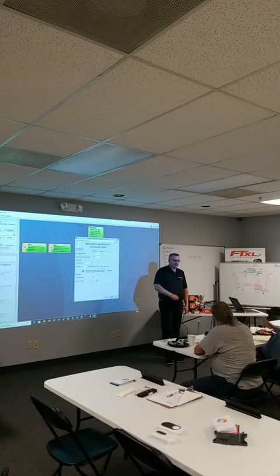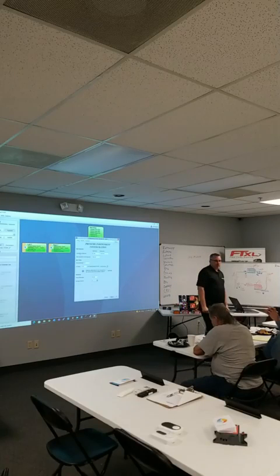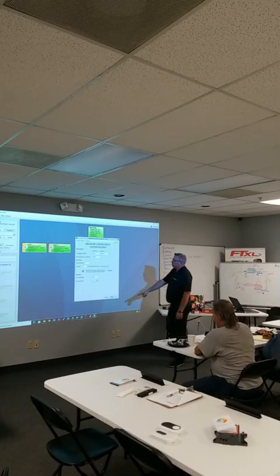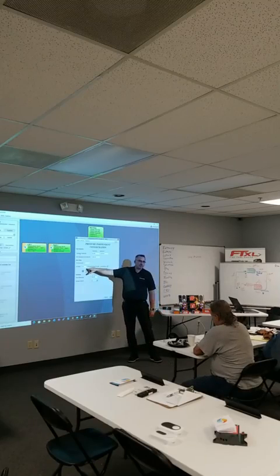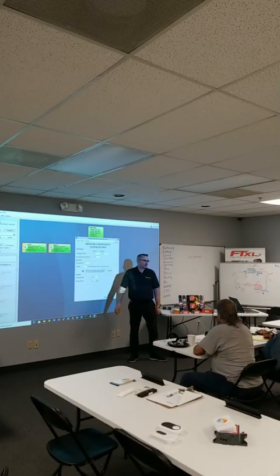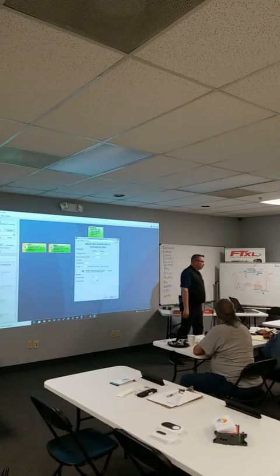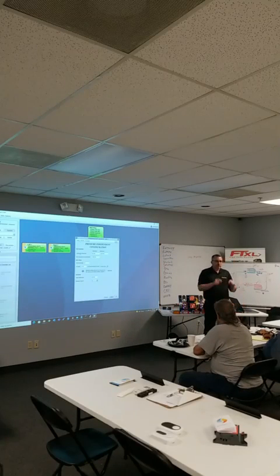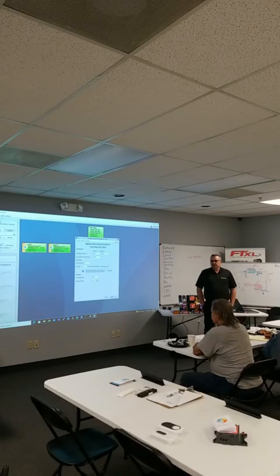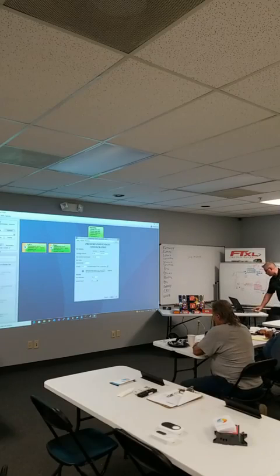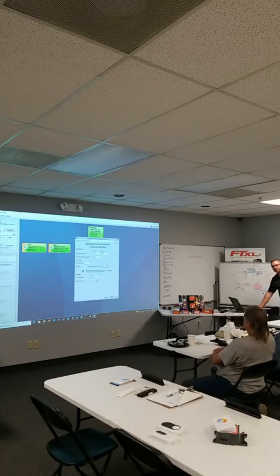Yes? What would be typical low and high K factor numbers, 200, 400, or? Typically, this is actually 2.39. Typically, the manufacturer of the box has that information. So if you bought a VAV box from someone, you can typically get that K factor information. Each manufacturer is a little bit different. So ballpark 1 to 4, 2 to 3. And there's two different ways they do it a lot of times. You'll see they have amplification in here, but if you drop that down, there's also the actual CFM, which is the CFM of the box at 1 inch of static. Yeah, we had to go by that. It depends on the manufacturer, on what they give you.